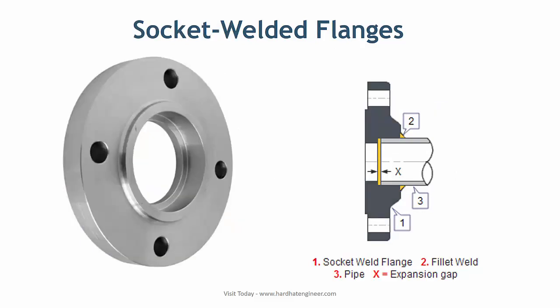Socket weld flanges have a female socket in which the pipe is fitted. Fillet welding is done from outside on the pipe. Generally, it is used in small bore piping and is only suitable for low pressure and temperature applications.